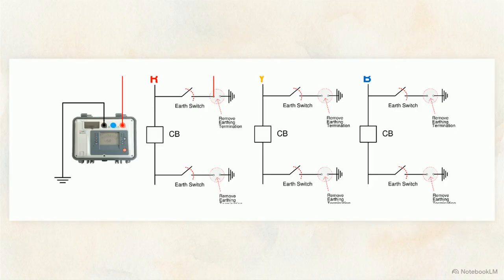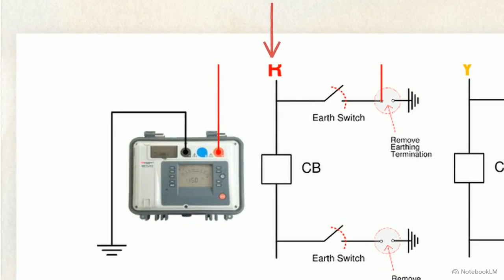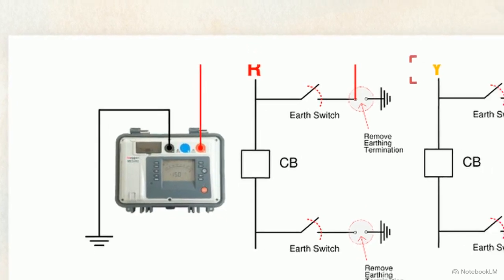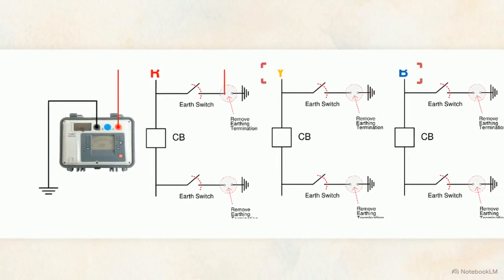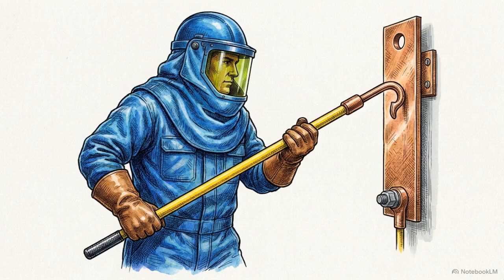Looking at this schematic for the phase-to-ground insulation test, the earthing termination is removed only on the tested phase. The tester injects 5 kV DC on phase R for 1 minute, keeping phases Y and B grounded, needing a stable resistance exceeding 100 megaohms. Because GIS components retain a significant capacitive charge, the circuit must be fully discharged using approved rods before altering any connections for the next phase.